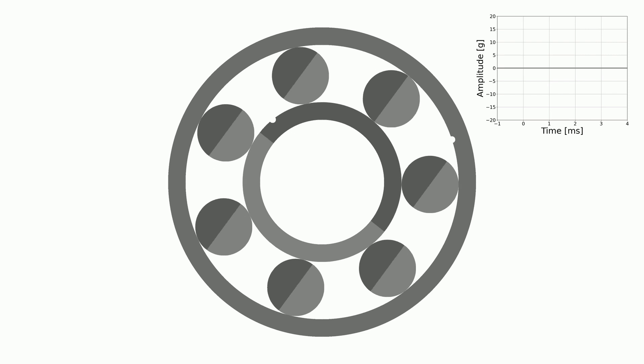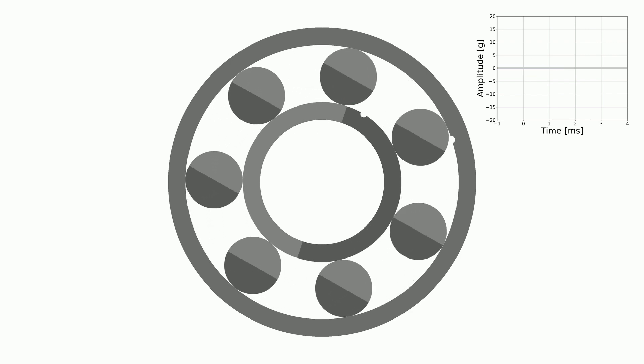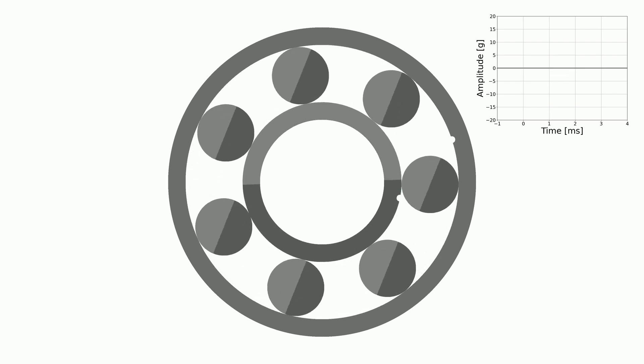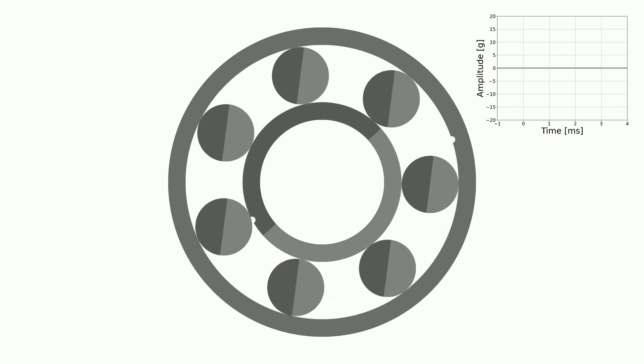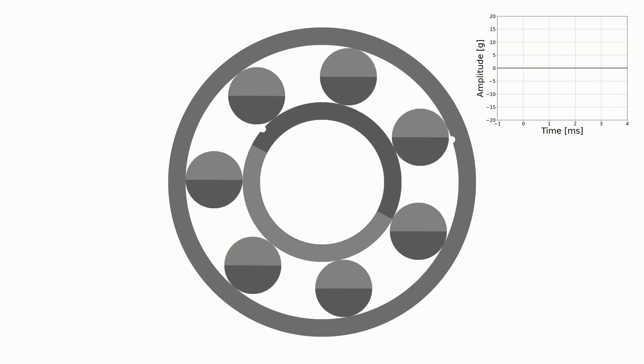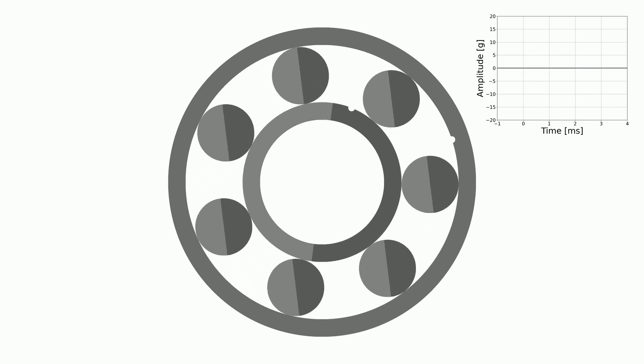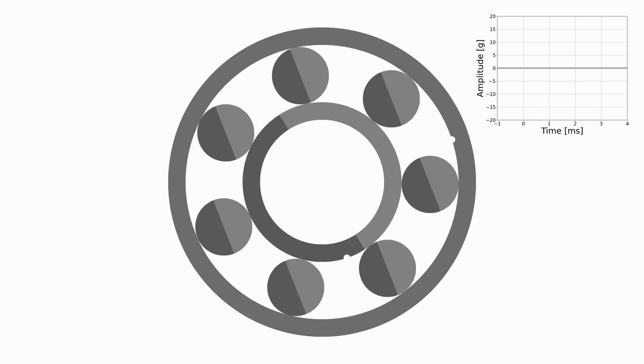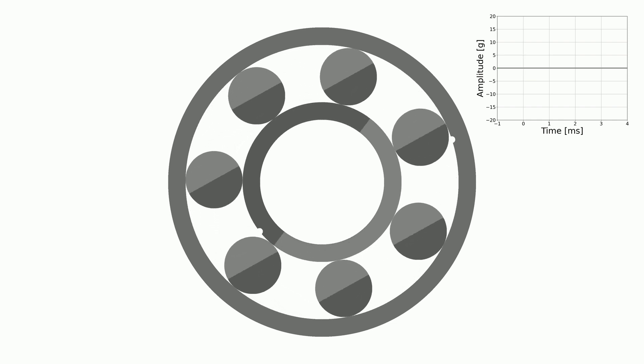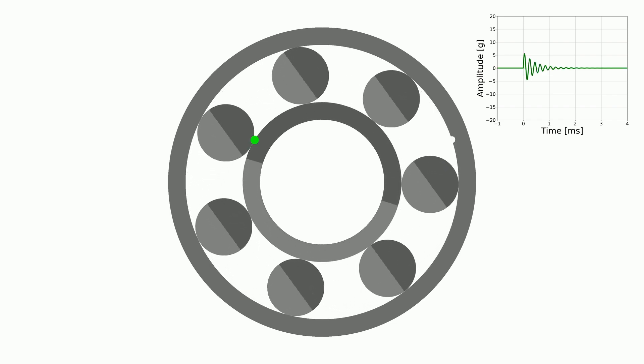Now, if we add a fault to the inner race, there will be two sets of shocks. The inner race shocks have a smaller amplitude as we can see in the graph showing the shocks. This is because the outer race is closer to the sensor used for measurement.